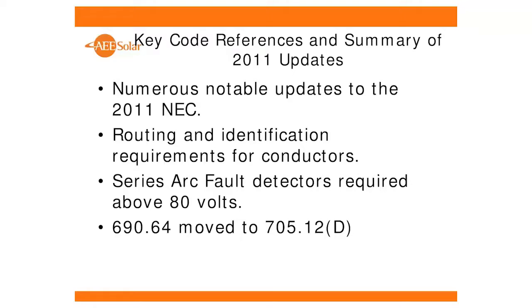One of the biggest changes in the 2011 code was series arc fault detection. And that being the code that we're on in California, now all of our inverters are going to be required to have arc fault detection on them. There could be a separate device that could do arc fault detection, but those products are very rare, and they're typically designed for large combiner boxes and things like that.